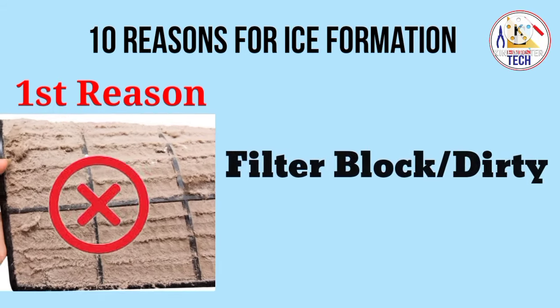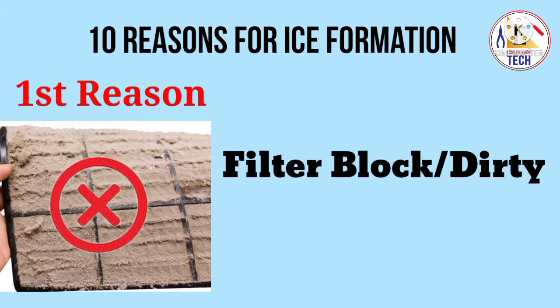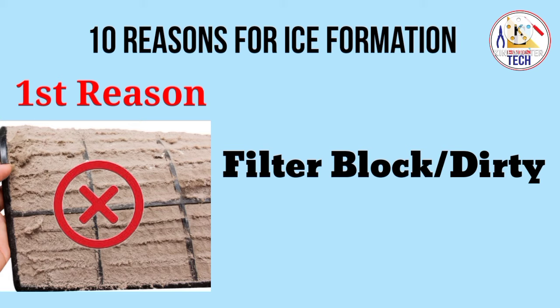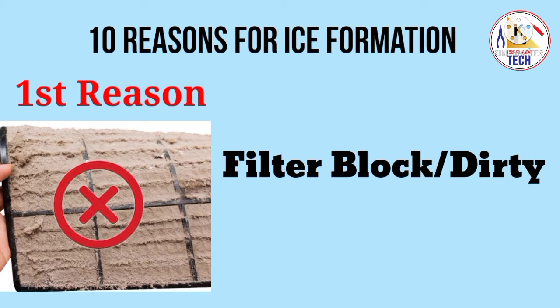The first reason for ice formation in our indoor unit is a blocked or dirty filter. When you see low air flow from your indoor unit, it means there is a filter block or choke. You can clean the filter or, depending on its condition, replace it, and you will see fresh air coming from your indoor unit with no ice formation.